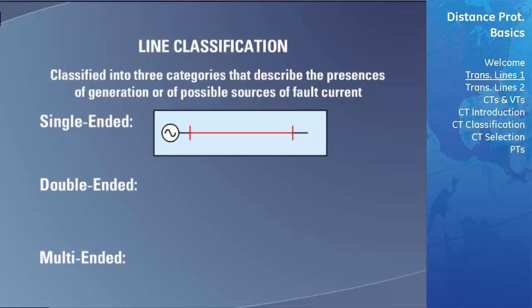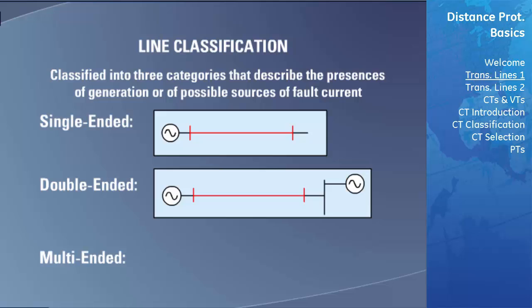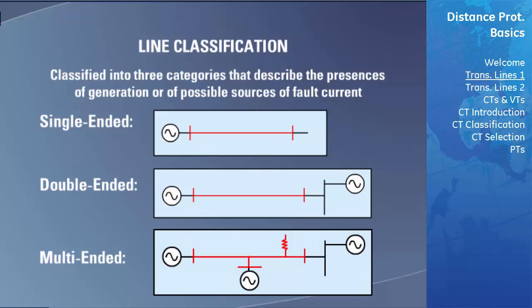A double-ended line has only two boundaries, each of which can have a source of fault current available. This type of line is used to deliver power usually in different directions at different times. If a fault occurs on this transmission line, current will be fed to the fault from two locations. A multi-ended line has more than two boundaries, each of which can have a source of fault current available. For this type of line, the direction of normal power flow can be highly variable, and at the time of a fault, it will be fed from many different locations.